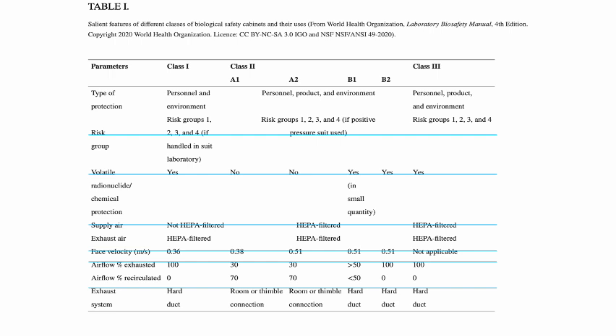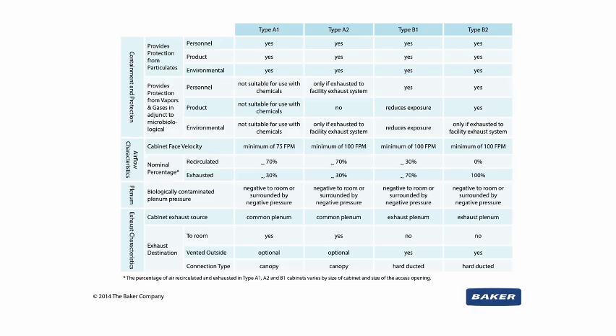Okay? And lastly, class 1, class 2 B1, B2, and class 3 are the cabinets that are hard ducted. Ibig sabihin, sa taas po ng cabinet nila, it has a large hose or exhaust duct that exhausts air completely outside the building, or outside the facility. So those are the differences between the classes of biosafety cabinets.